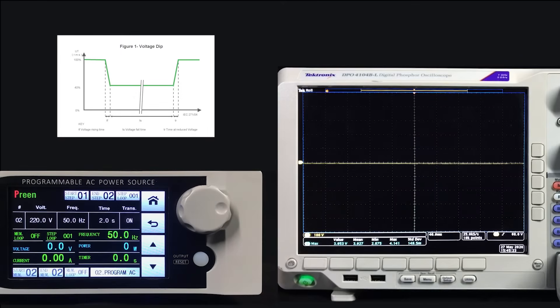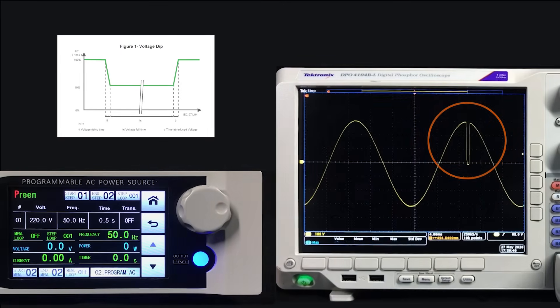From the oscilloscope, we can see the voltage drops 100% in a short period of time. The AFV-P series can generate the voltage dip waveform according to our settings.